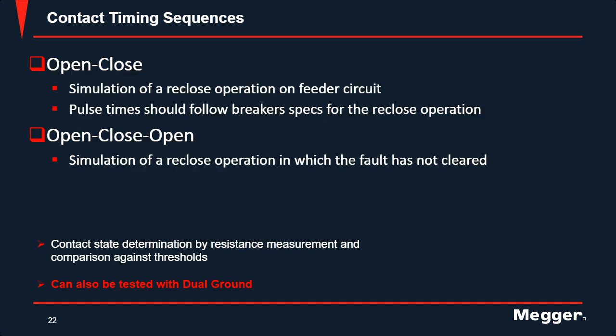And as I mentioned, there's two other ones. You've got your open close and your close open. These are generally for if you have a recloser operation for your breaker set up inside your relays, you can verify that they are operating as intended. So the contact state is determined by resistive measurements in comparison against a threshold for a typical timing test. We're going to go over another method called DCM, which is dynamic capacitive measurement, which can be used with dual grounding, which we'll also talk a little bit about in a little bit.